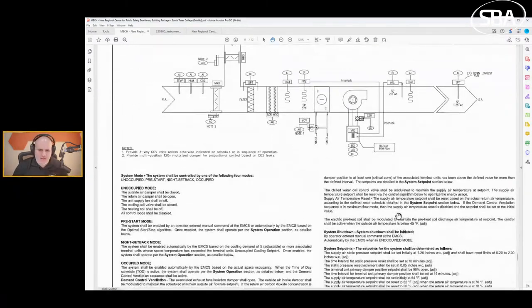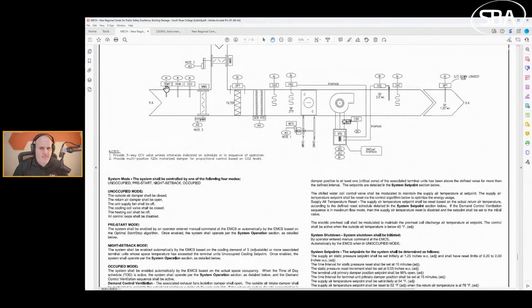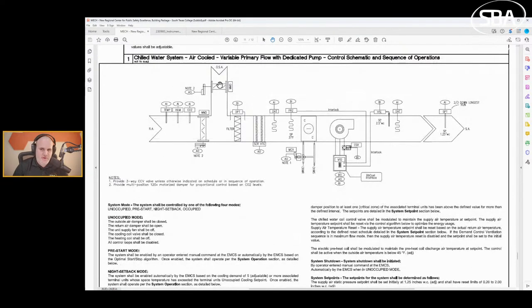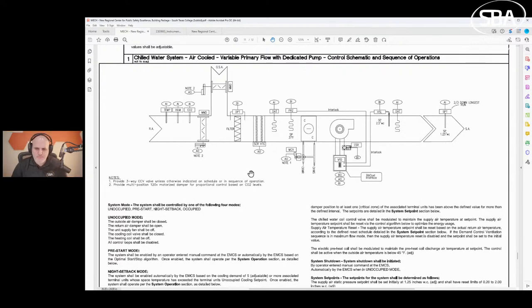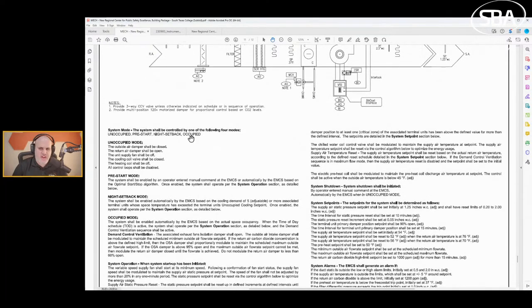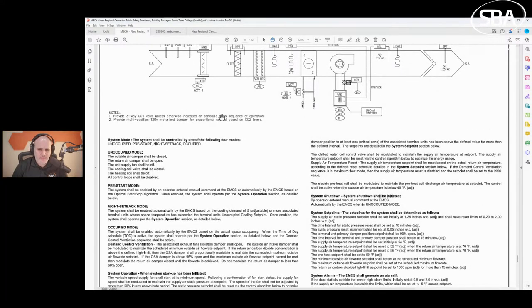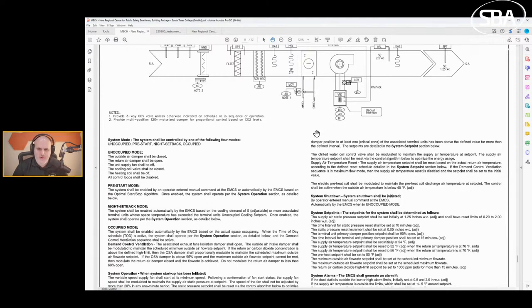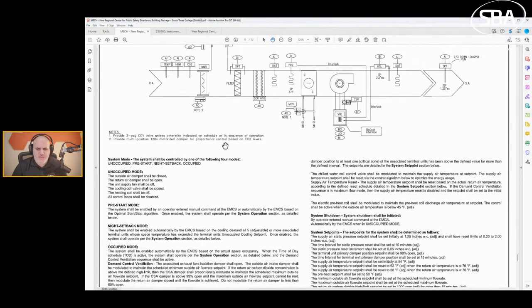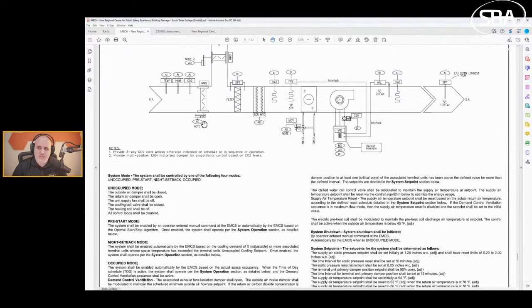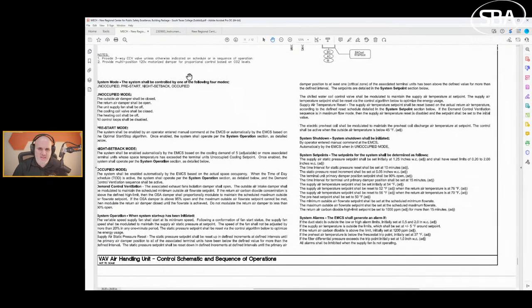I don't know why I have these hard wires when I have a BACnet interface. I've got temperatures though - return temperature, supply, flow meter. I've got my chilled water pump with BI, BO and AO and a BACnet interface. I don't see my pressure sensor to control this VFD, that's kind of odd to me. We can see kind of the sequence. We get to the air handler and it has a crap ton of stuff. Temperature, humidity, CO2, different dampers, heat, discharge, low temp freeze stat, chilled water, fan, high static, low static.